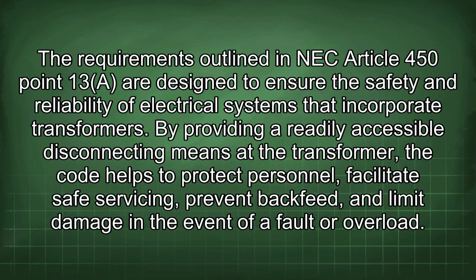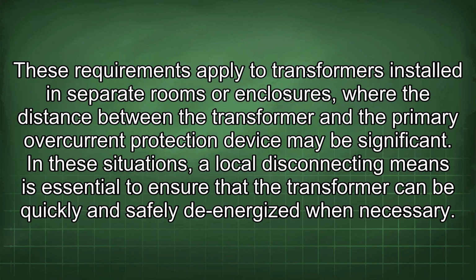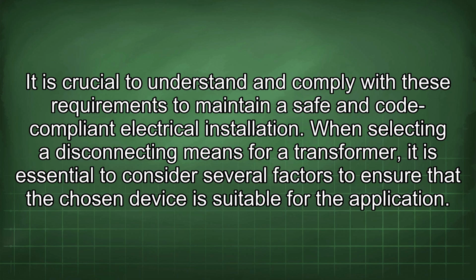The requirements outlined in NEC Article 450.13 are designed to ensure the safety and reliability of electrical systems that incorporate transformers. By providing a readily accessible disconnecting means for the transformer, the code helps to protect personnel, facilitate safe servicing, prevent backfeed, and limit damage in the event of a fault or overload. These requirements apply to transformers installed in separate rooms or enclosures, where the distance between the transformer and the primary overcurrent protection device may be significant. In these situations, a local disconnecting means is essential to ensure that the transformer can be quickly and safely de-energized when necessary. It is crucial to understand and comply with these requirements to maintain a safe and code-compliant electrical installation.